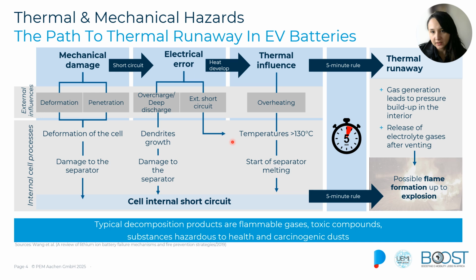Because of all this, at the end we will have the thermal runaway. And as explained, according to the 5 minutes rule, all of these events have to be controlled and held back for at least 5 minutes before the possible explosion or release of electrolyte gases, after venting the cells and so on.